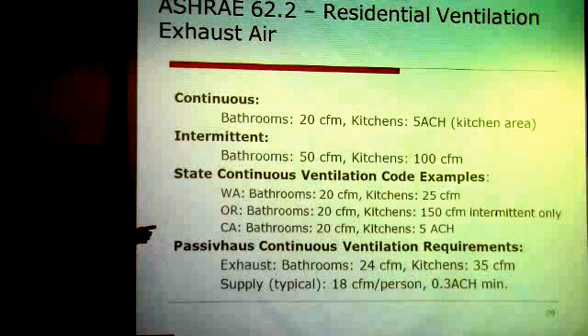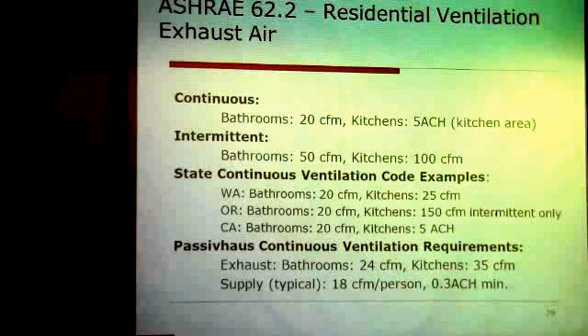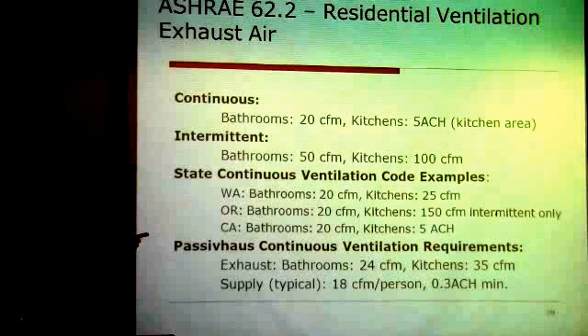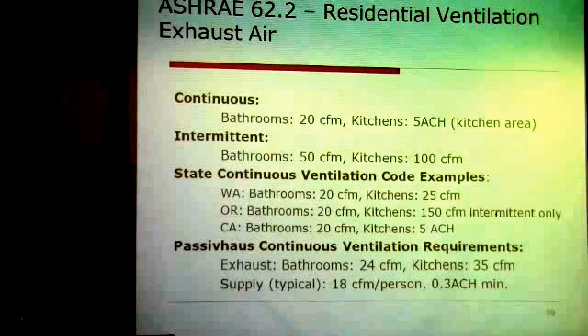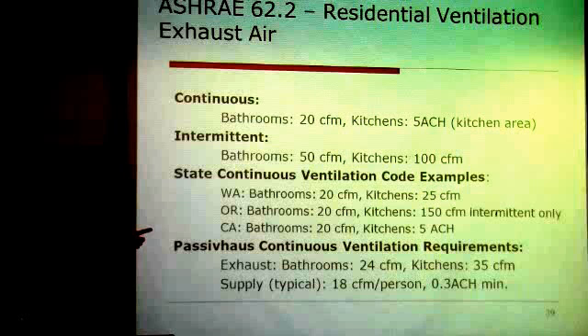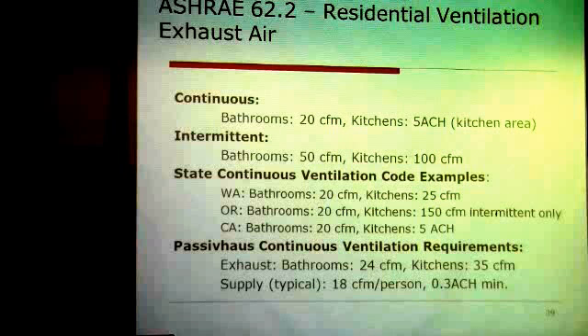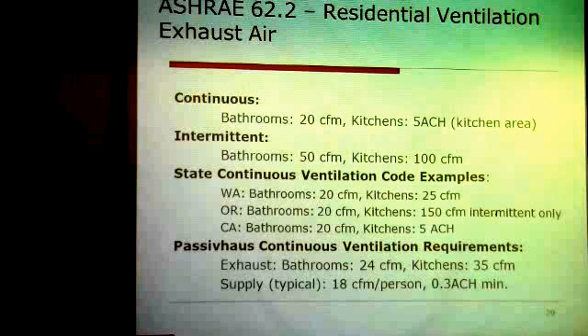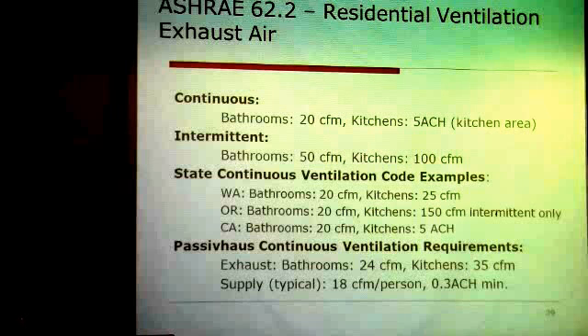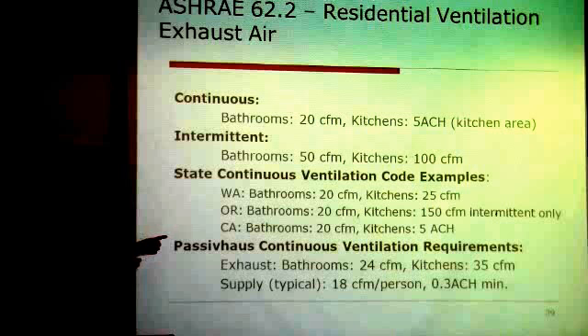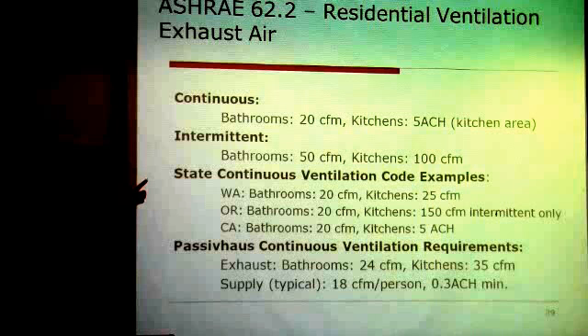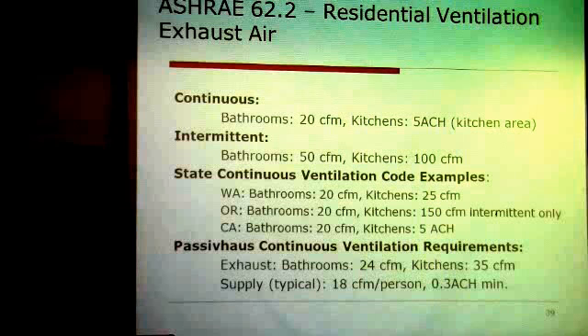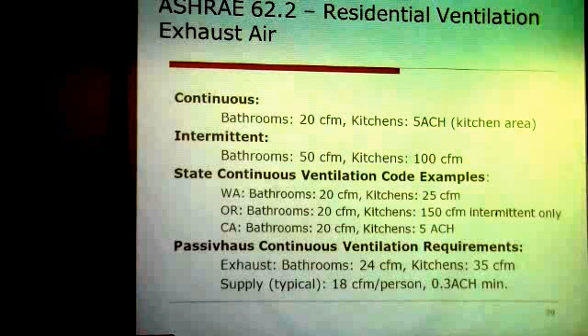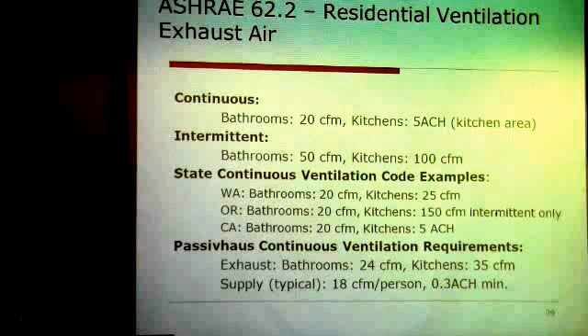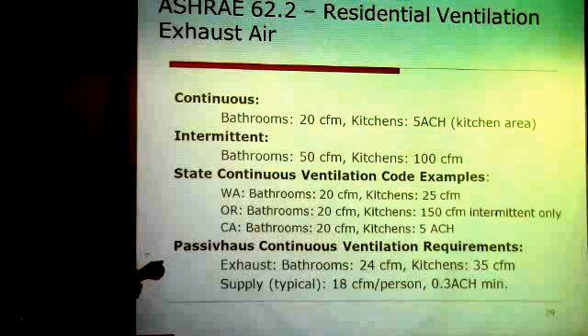Oregon just changed theirs. Before last summer, it was 20 and 25, and now they said, hey, we don't want continuous, we want intermittent only. So there they say, hey, you need to have a direct exhaust vent on your kitchen that vents 150 CFM. That was a new change. And then in California, they're using exactly this ASHRAE of 20 CFM, and then kitchens, they need an exhaust rate of 5 ACH. So when you figure this all out, usually the exhaust rate dictates the system design.